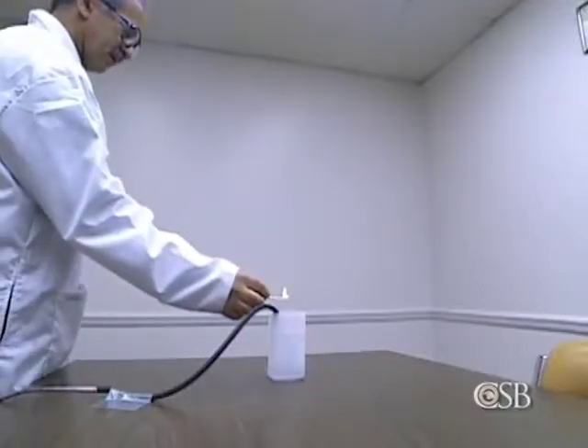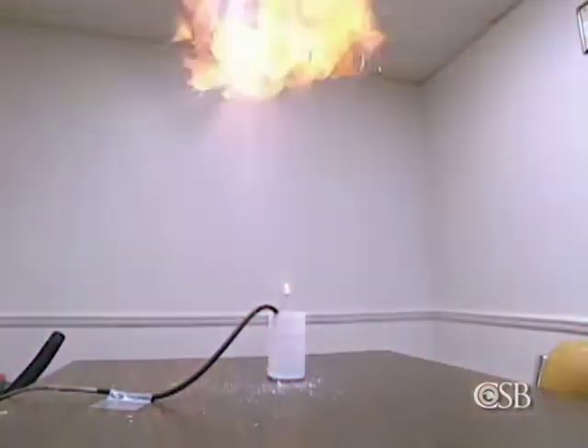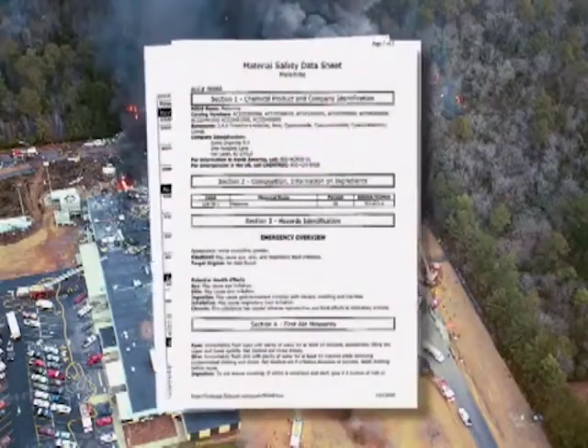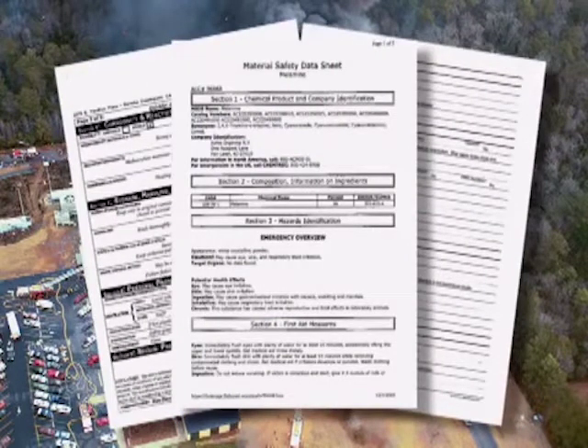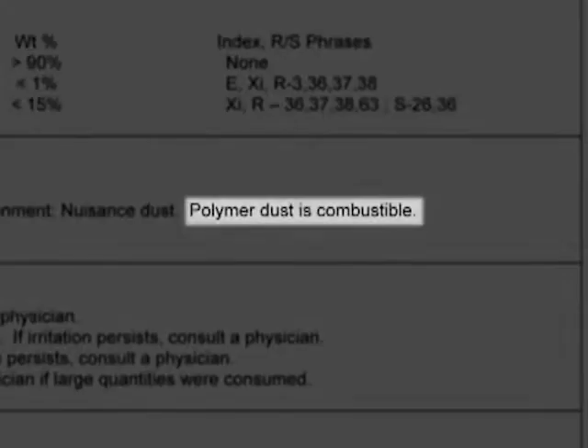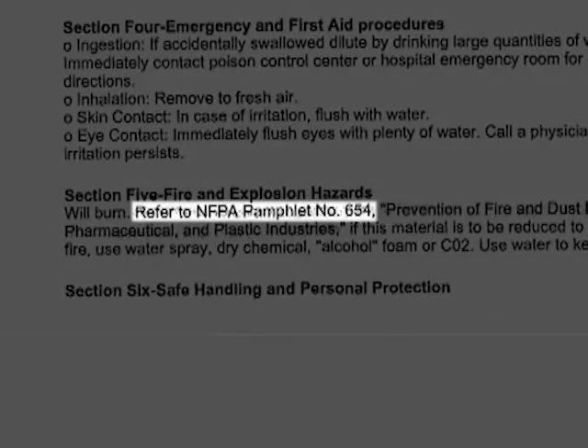Jim Don, a leading expert on combustible dust, explained that if you've got a dust, you need to know its ability to explode — whether it takes little or a lot of energy to ignite, and whether it will create a major overpressure when it explodes. Those are the things that need to be on an MSDS. The CSB found that the problem of inadequate MSDSs is widespread: of 140 MSDSs for combustible powders, very few included adequate dust explosion warnings or referred readers to the appropriate NFPA codes.